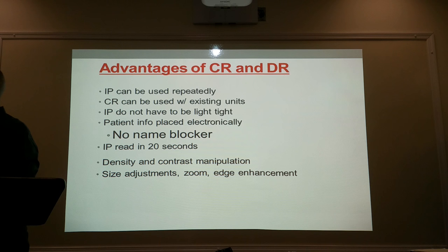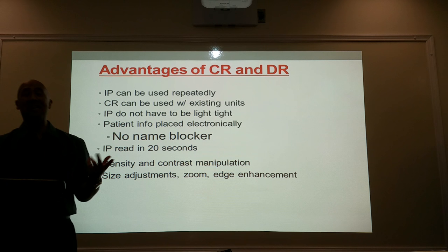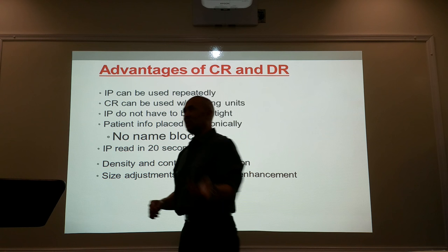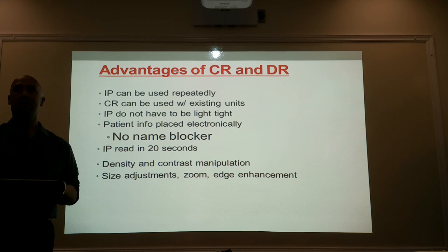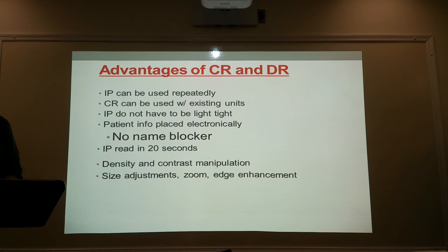Here's a new term: DR, which stands for direct radiography — not digital, direct. With computerized radiography we're using imaging plates that we still have to process through the reader. With direct radiography, there are no cassettes. You take an x-ray and the sensors are in the table or on the chest board. The signals go straight directly into the software program and your images come up simultaneously on your screen — boom, simultaneously. That's direct radiography. It's a nice thing to have, but it's not as portable and it does have some limitations.